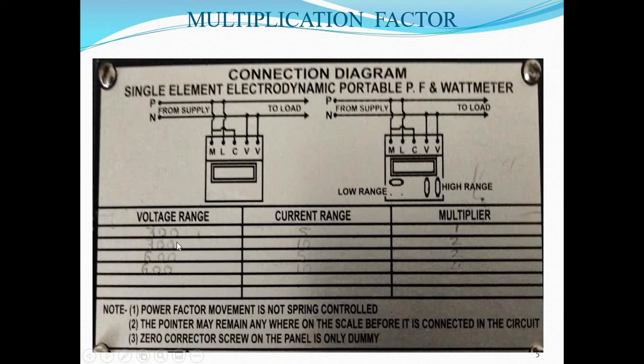If the voltage range selected is 600 and current range is 5 ampere, then the multiplication factor equals 600 into 5 into 1, divided by 1500, which is 2. And if the voltage range is 600 and current range is 10, then the multiplication factor is 600 into 10 into 1, divided by 1500, which equals 4.